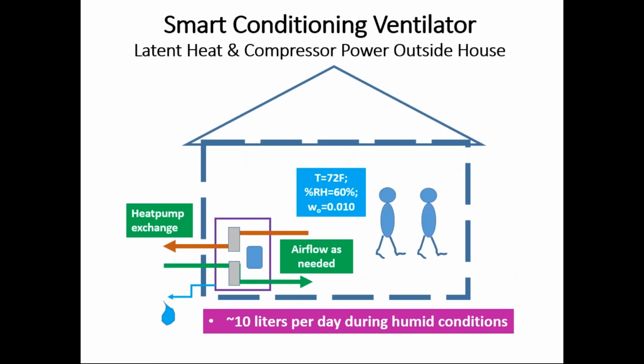A smart conditioning ventilator that has a heat pump incorporated into it. In the case of ours, we can remove about 10 liters of water per day. One of the nice features is that when heavy humid air is coming in from outside, conditioning it with a heat pump lets us pull moisture out of it very efficiently when the moisture is most concentrated. This gets rid of quite a bit of water, and the additional water that needs to be managed is managed by the mini split heat pump.